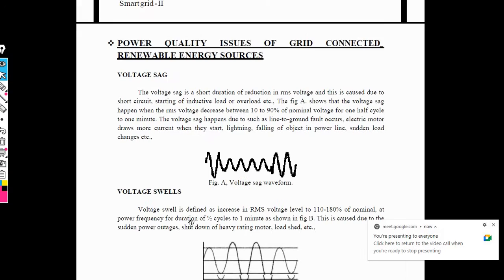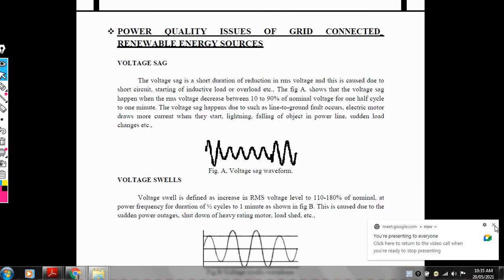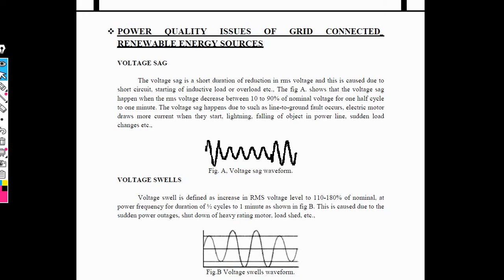Then also we need voltage sag. That means a change in voltage level. In voltage sag we have to measure the short duration time and long duration time, for which we use RMS voltage. Also we need to study the short circuit. Then the above figure shows the voltage sag, in which the RMS voltage decreases from 10 to 90% of nominal voltage. That means the voltage decreases from 10 to 90% of nominal voltage in 1/2 cycle of the 1 minute. That means very little time is required for the voltage sag. And voltage sag will also occur due to a line to ground fault.